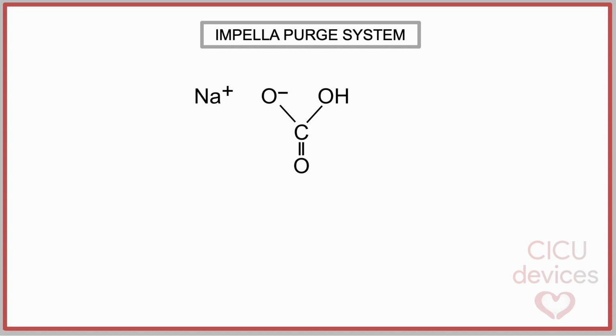Sodium bicarbonate does not exert a direct anticoagulant mechanism comparable to heparin. Its protective role in Impella purge solutions using bicarbonate-based purge solution is primarily related to the maintenance of a stable alkaline pH of approximately 7.8 to 8.0. This alkaline environment reduces local platelet aggregation and thrombus formation within the motor housing.